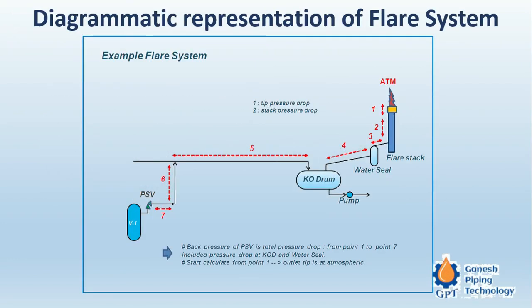This is a diagrammatic representation of the flare system. There are PSVs and vent lines where we can drain out before plant shutdown. We can see the tip, pressure drop, and stack pressure drop. This is the tip from where gases are burnt to atmosphere — the flare stack. All flare lines are sloped at a ratio of 1:200, and they are routed to a single flare header, which is directed to a knockout drum.